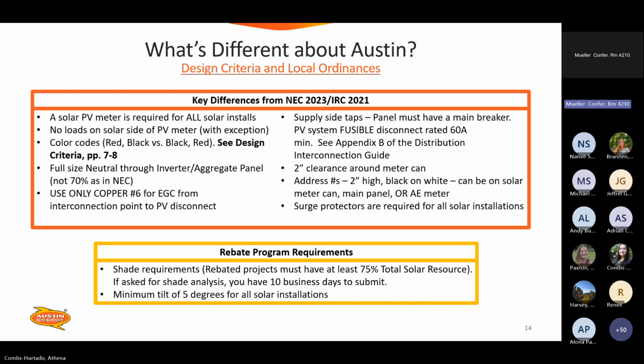Our color code, as I said, is red, black, not black, red. That's in the first few pages of the design criteria. We do require a full-size neutral through the inverter and the aggregate panel, not 70%, as would be allowed by national code. You need to use a number 6 copper for your equipment grounding conductor from the point of interconnection to or through the PV disconnect. So basically on the ground, if your feet are on the ground, you can pull a number 6 EGC. And then beyond that point, when you go up to your array, you can transition to what the NEC would allow. Supply side taps, line side taps.